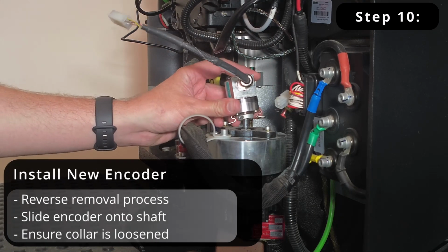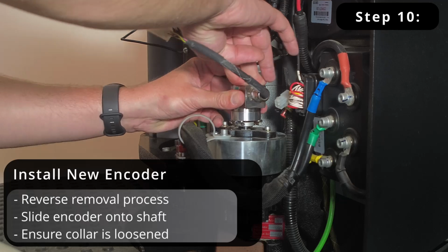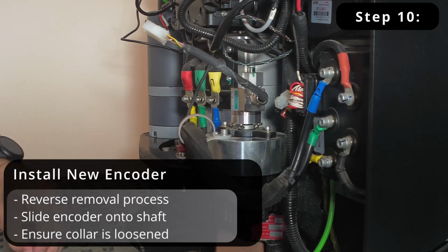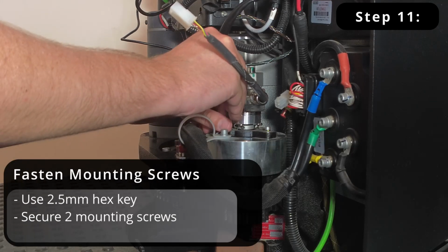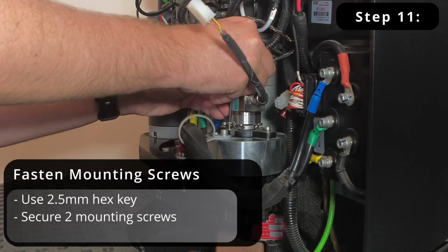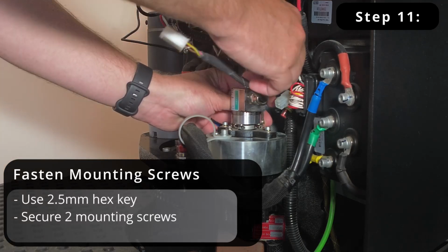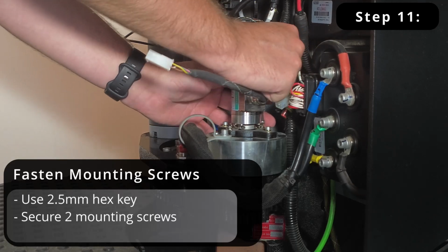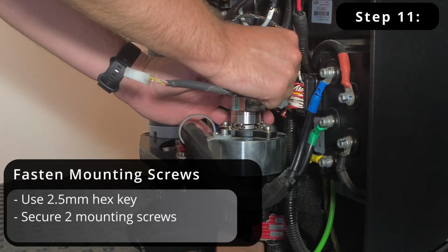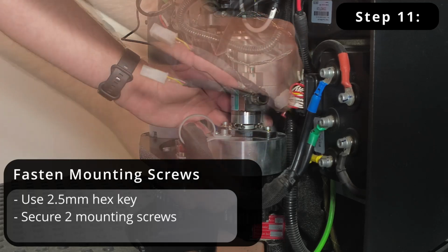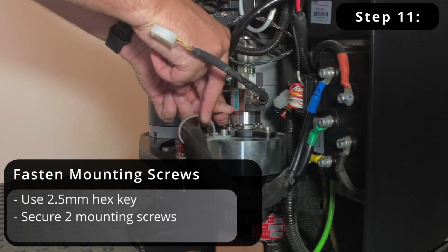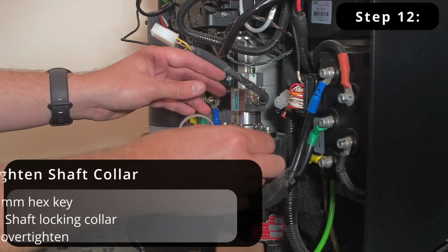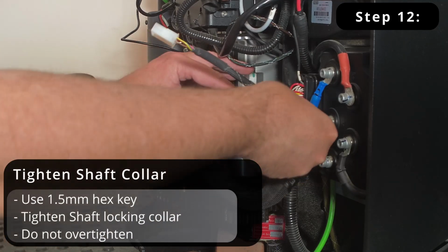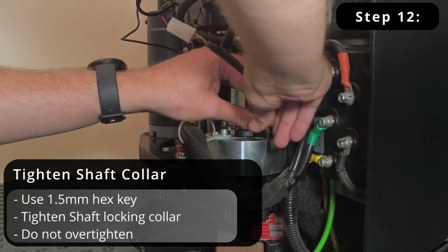Install the new encoder by reversing the removal process. Slide the encoder fully onto the shaft, ensuring the collar is loosened so it seats properly. Using the 2.5mm hex key, fasten the two mounting screws to secure the encoder in place. Tighten the shaft collar screw with the 1.5mm hex key. Be careful not to over-tighten.